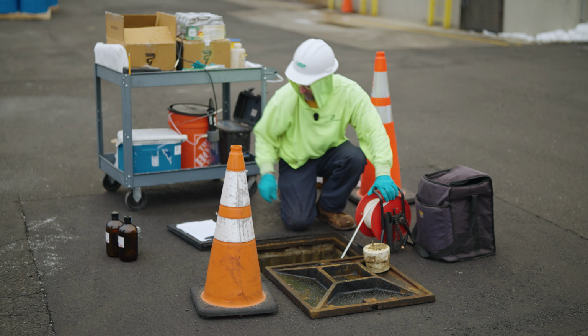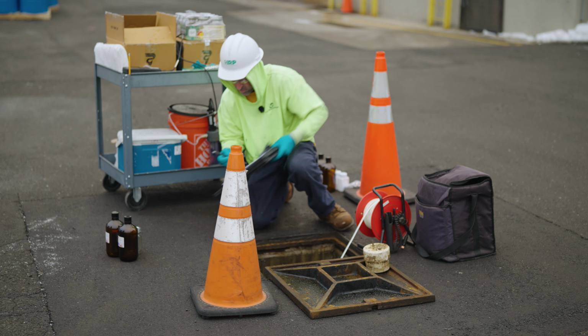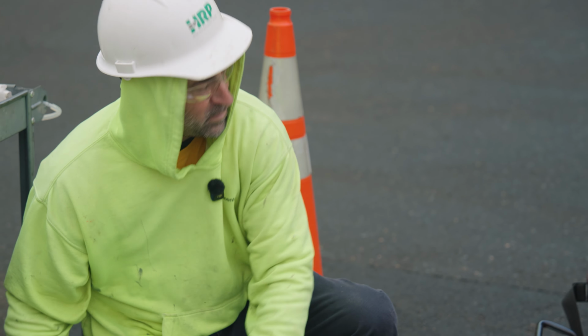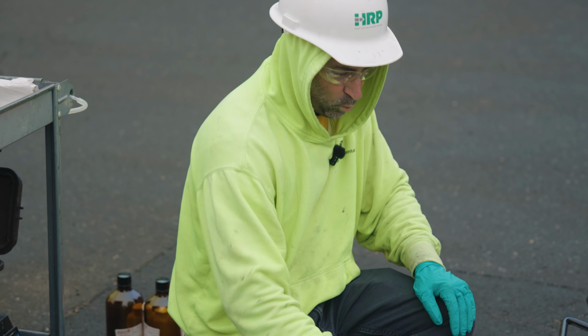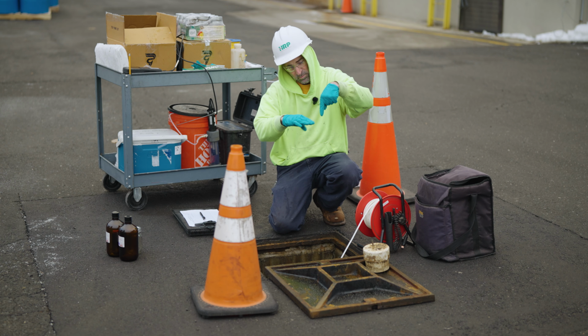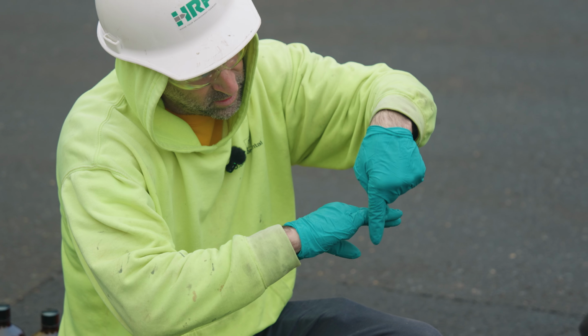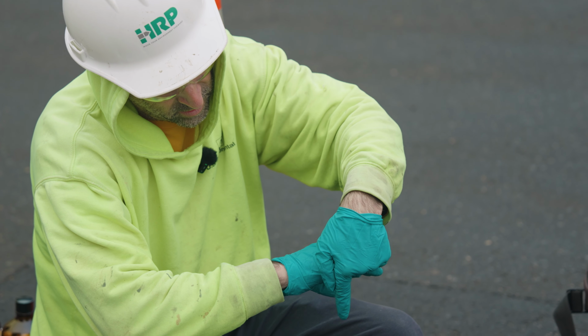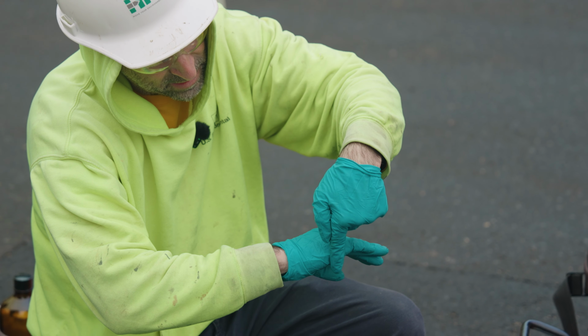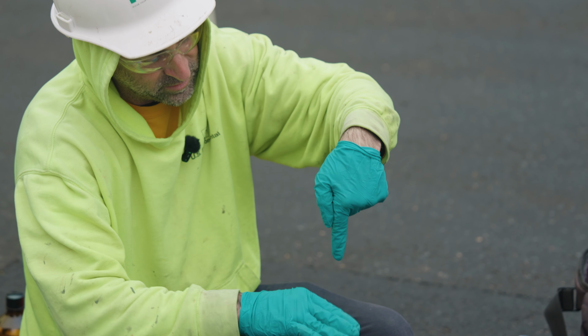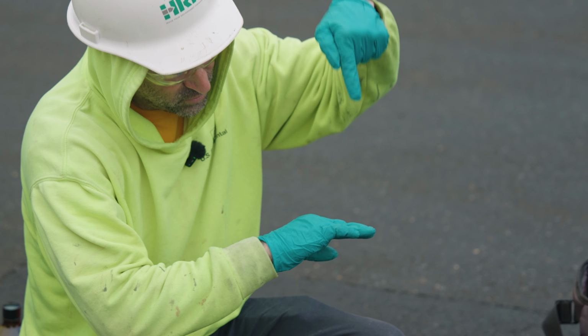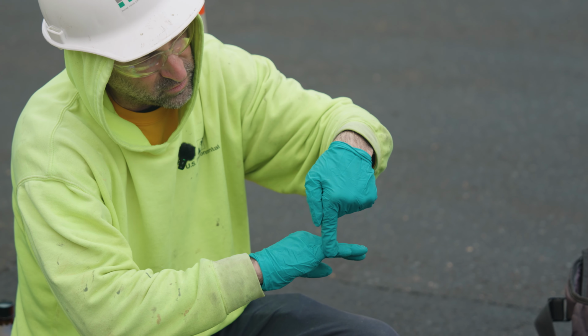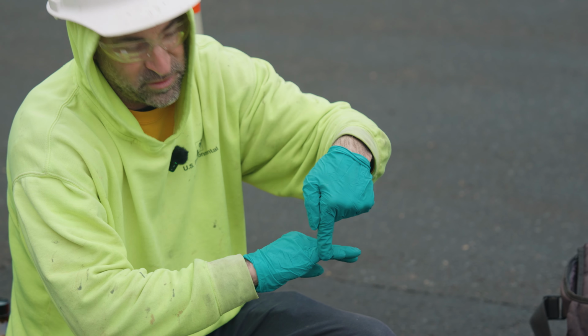Our oil is at 5.36 feet below grade. And now we'll need to get the water level. So you want to go through the product until you get your solid tone. Your solid tone goes to an intermittent, and then come back up again until you get a solid tone. That is going to be your interface level. If you just go down and when it changes over right there, sometimes the oil gets stuck on the probe and it's a false reading.